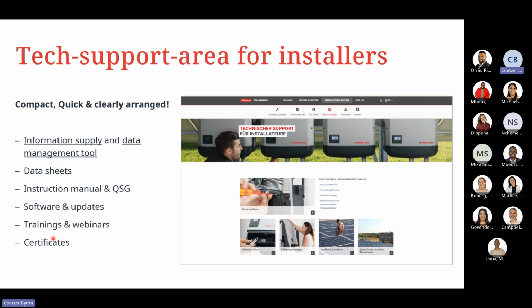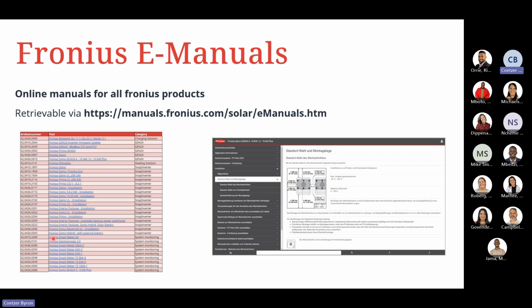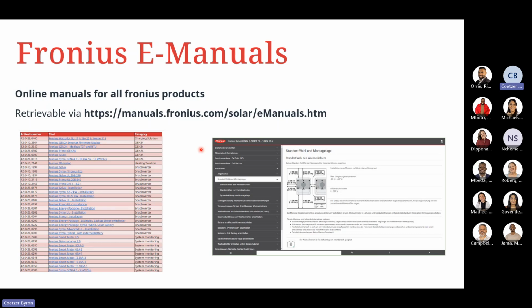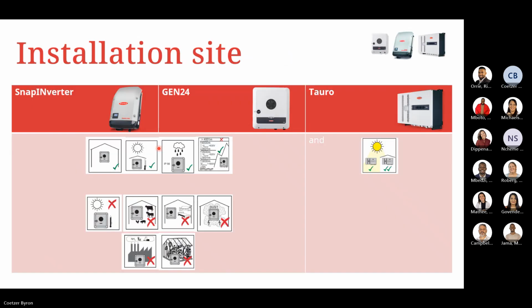If the client requires an IEC certificate or NRS, it is available on the website to be downloaded. Next, we recommend the Fronius e-manuals page. This page is very handy for clients that are doing a smart meter in the system or doing a battery connection. It will always give you a brief schematic of how exactly it needs to be wired up. If you're doing a smart meter, it'll tell you how to wire the CTs to the meter as well as on the COM side. If you need to do a 120 ohm jumper, for example, it'll all be explained on the Fronius e-manual side. Again, these are online manuals for all Fronius products, and they show you exactly what is required when doing the installations.